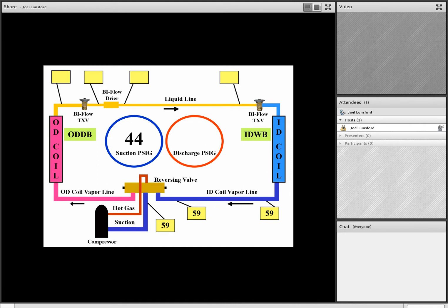And at 44 pounds of suction pressure, as we refer to the chart, we see that gives us a temperature conversion of about 21 degrees. So as we take a look at 44 pounds of suction pressure and 21 degrees, we then find the difference between 21 degrees, step number 1, that we got off of our chart, and step number 2, the physical line of the suction line temperature in our example. And we see the difference is the difference between 59 degrees suction line temperature and about 21 degrees saturation pressure temperature conversion off the chart. So the difference between 21 and 59 is about 38 degree difference.